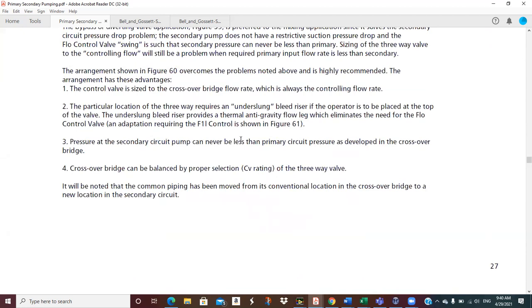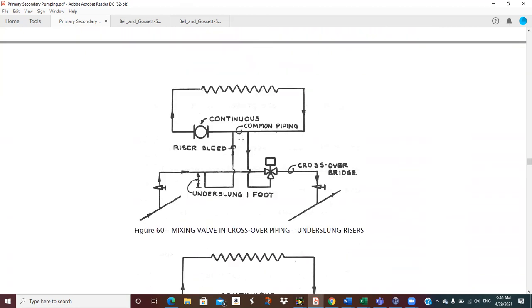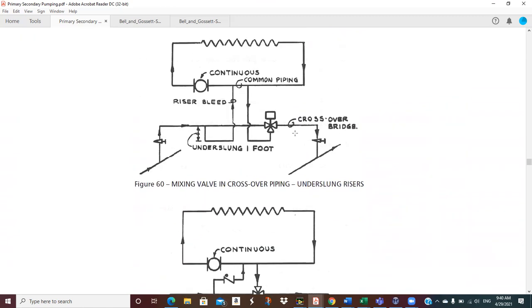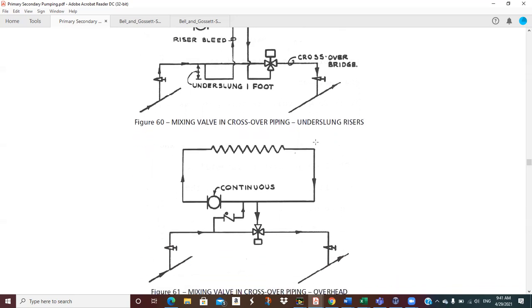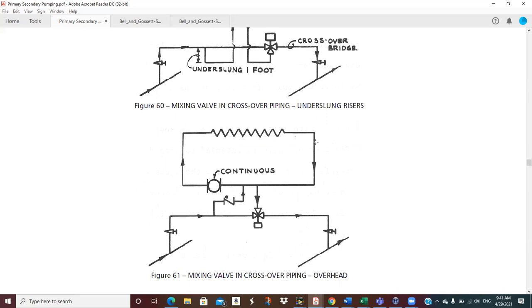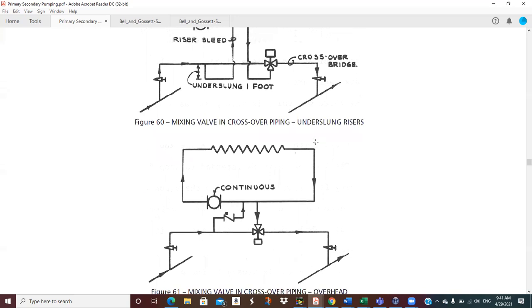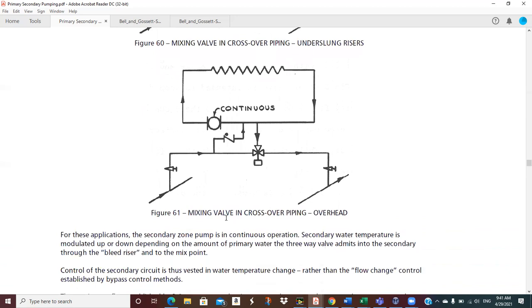And the crossover bridge can be balanced by proper selection of CV of the three-way valve. So if we select our CV appropriately on the valve, then that's part of the balancing, even though we're showing a balancing valve in the crossover anyway. Okay, so with a three-way valve, that's the recommended procedure. Okay, what do we got here? Oh, okay, this just shows it with overhead piping. If you have the overhead piping in this leg, you got to put that check valve, that flow control valve, to prevent any gravity circulation up into that secondary. So that's not much.